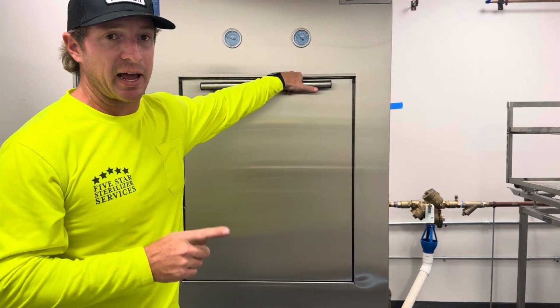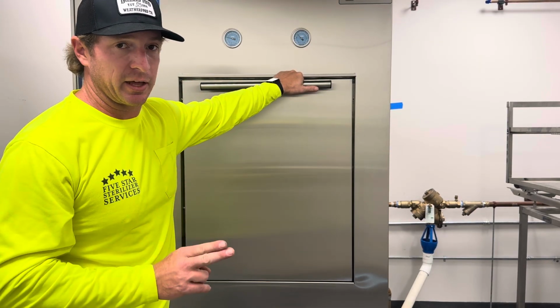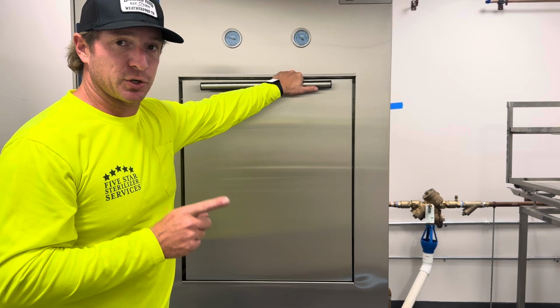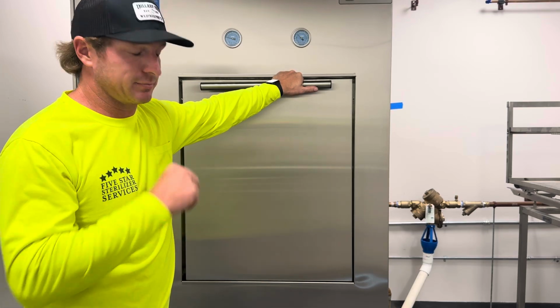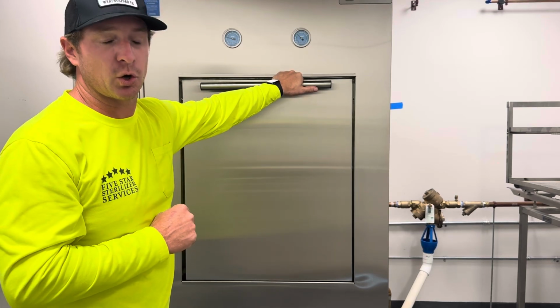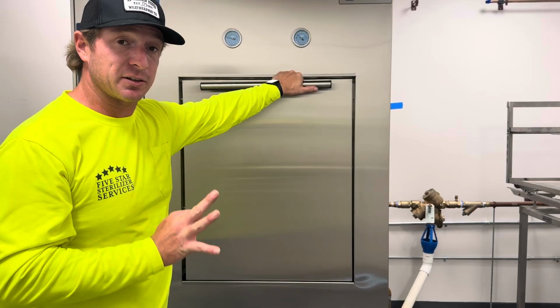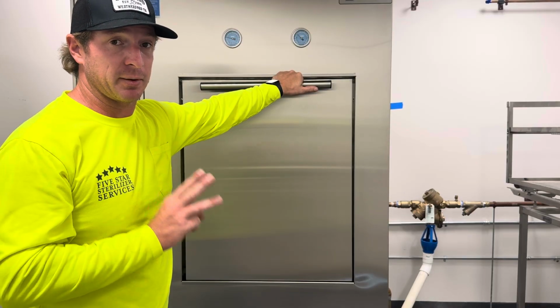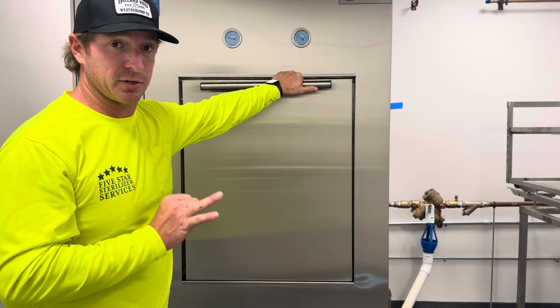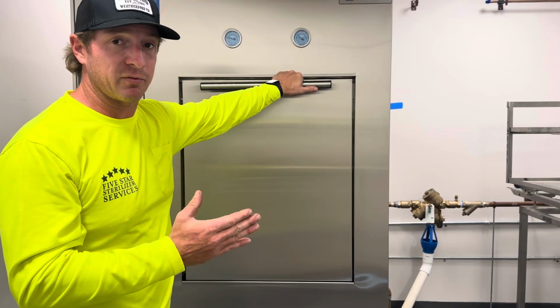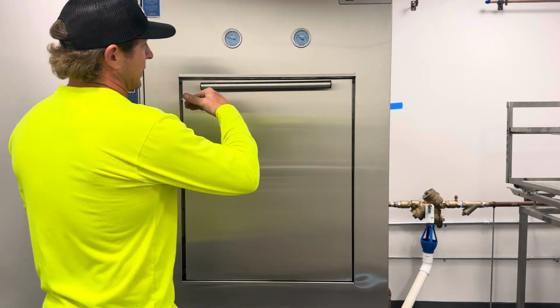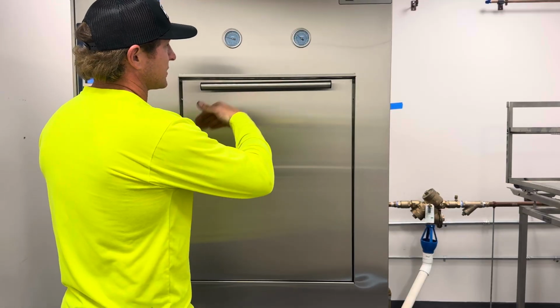When it comes to steam sterilizers, you cannot have one without the other. Time and temperature and pressure correlate. The 3 factors of sterility are time, temperature, and pressure. But temperature and pressure, those 2 correlate. You cannot have one without the other. So as we're rising in temperature, we're also building pressure.